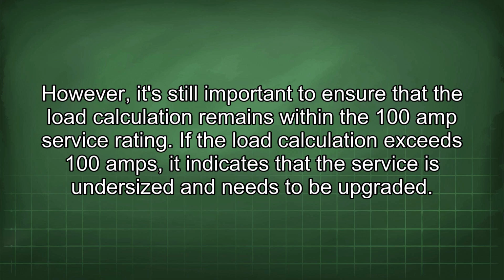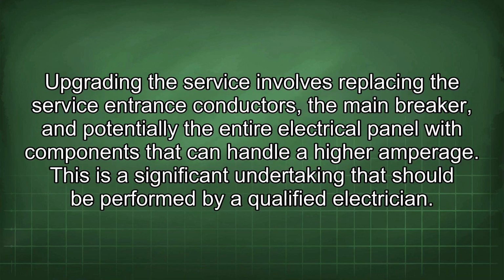If the load calculation exceeds 100 amps, it indicates that the service is undersized and needs to be upgraded. Upgrading the service involves replacing the service entrance conductors, the main breaker, and potentially the entire electrical panel with components that can handle a higher amperage. This is a significant undertaking that should be performed by a qualified electrician.